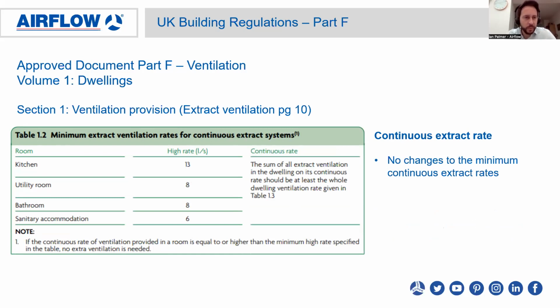The following table 1.2 shows minimum extract ventilation rates for continuous extract systems. So these extract rates are a lot lower, but because the extract is in continuous mode, they can meet these lower standards. So remember, these are the minimum standards. You can have a fan doing a higher rate, which would be better, but as long as it meets the minimum standards, it's complying with the building regulations. And this is the installed performance as well, by the way.